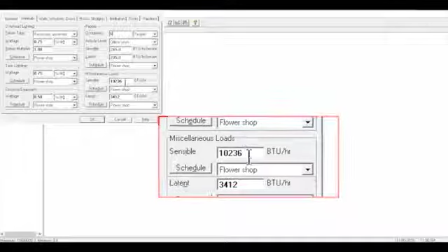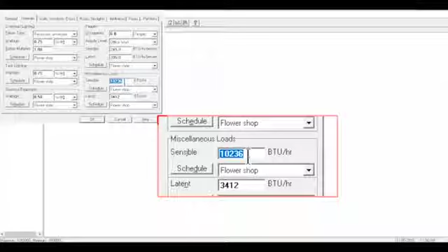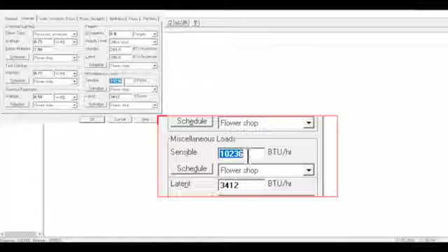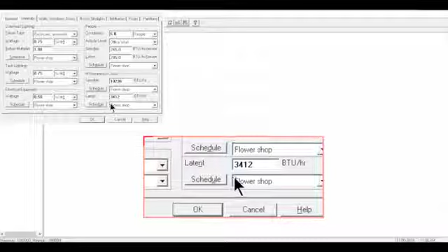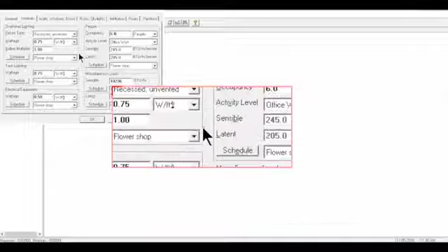Miscellaneous loads - for example, an extra heater or something like a cooking oven or cooking range, you can mention that sensible and latent there. Just put 10,236 sensible and 3,412 latent heat, I mentioned that for example I may have a cooking oven. Yes, this is coming over there.